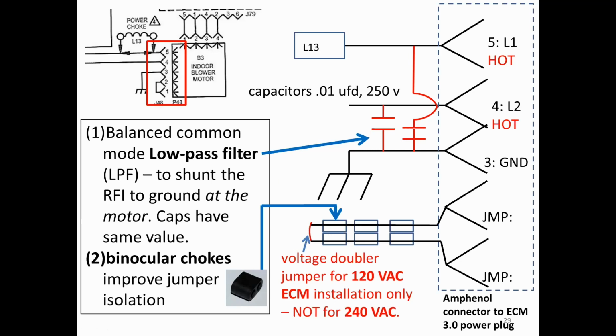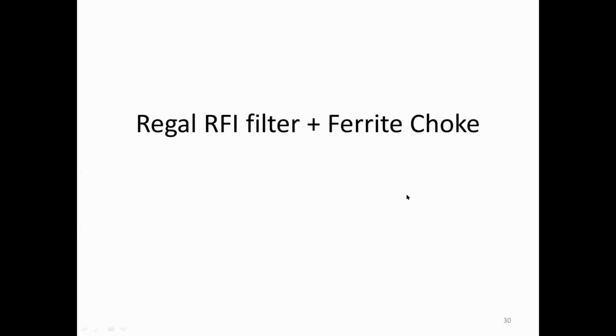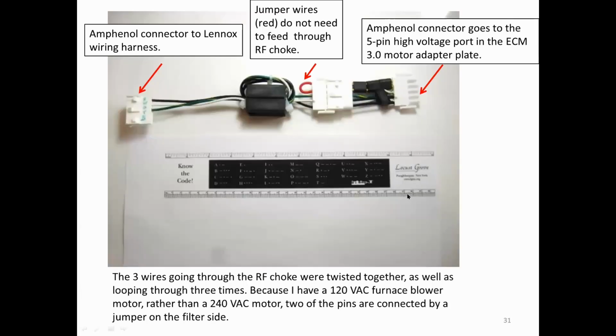There's some binocular chokes for a voltage doubler circuit, and it improves the isolation between the two lines. The voltage doubler circuit is jumped only for a 120 volt ECM, which mine is. If you jump it for a 240 volt ECM, you will cook the motor and probably your furnace. But the point is, this is a balanced common mode low pass filter. The intent is to shunt RFI to the ground at the motor at the point where the 120 volt lines plug in. Actually, I think one of these is 120 volts and one of them is common and neutral, but the principle is the same. So what did this do? Oh, here's one more diagram.